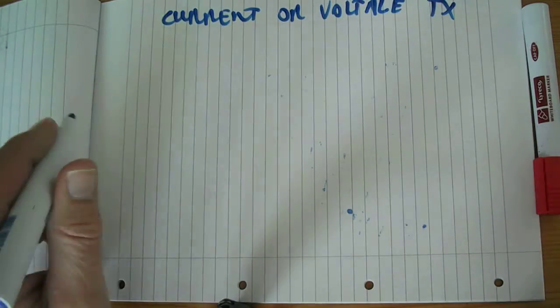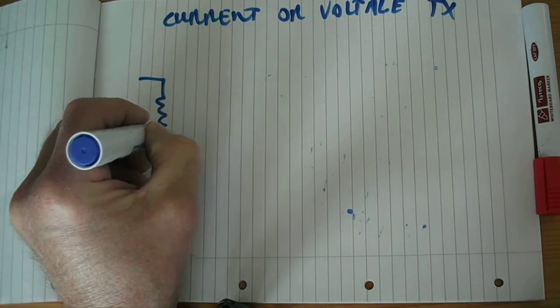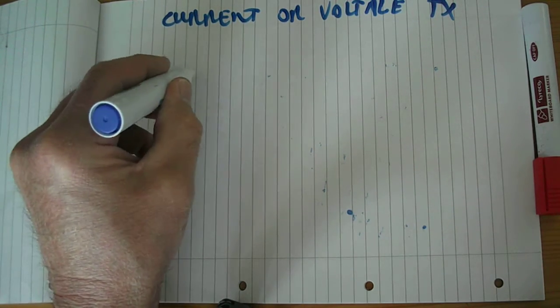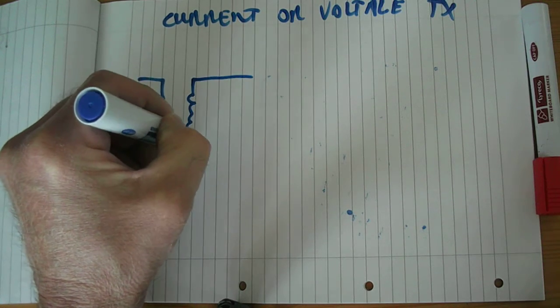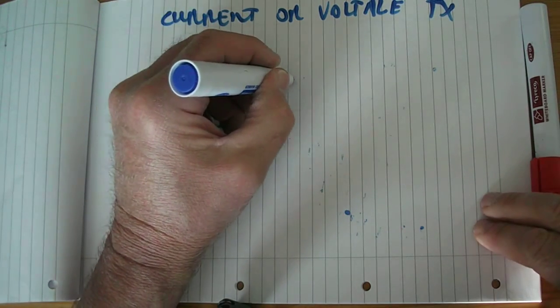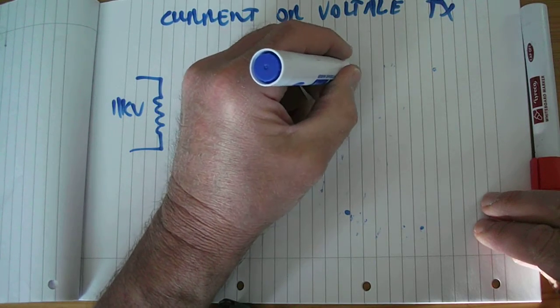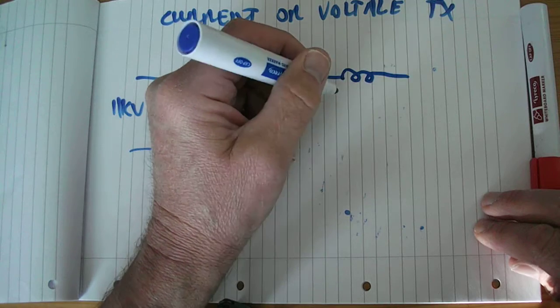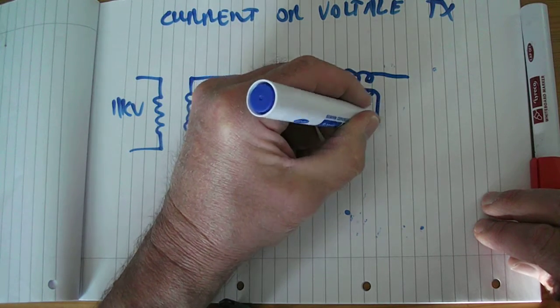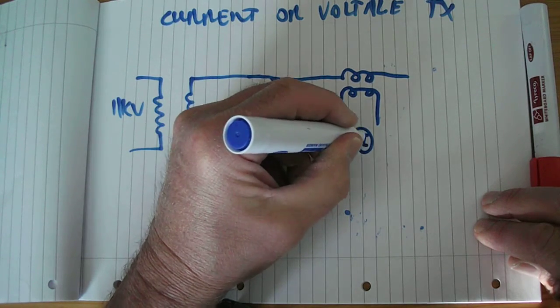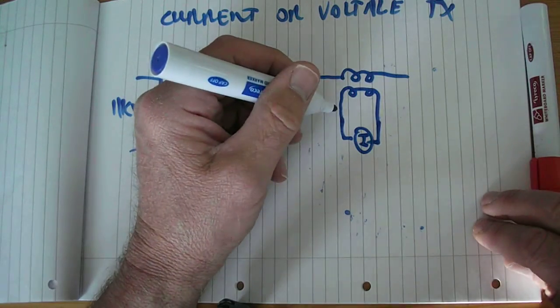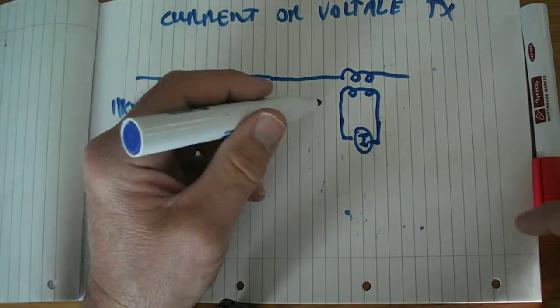Just one point on, say, current or voltage transformers. TX means transformer. You remember that if we have a transformer like this, say 11 kV coming in, and say 230 volts here, single phase, I'm just showing single phase. Then if we want to measure the current flowing through that line, we effectively have a current transformer on the line, and the secondary of that transformer is taken off, and that measures current. Usually it's done electronically and digitally converted to send off to your control room.